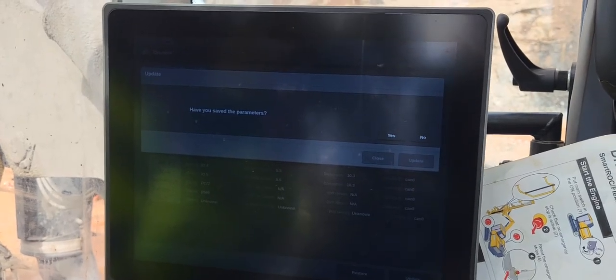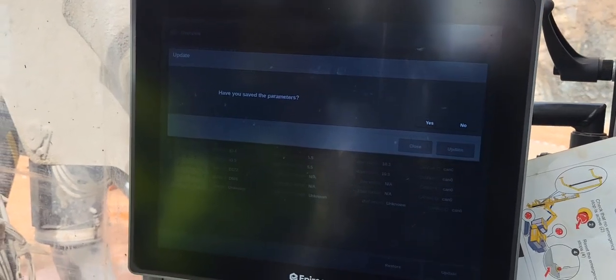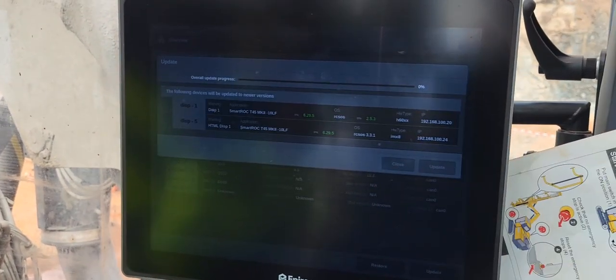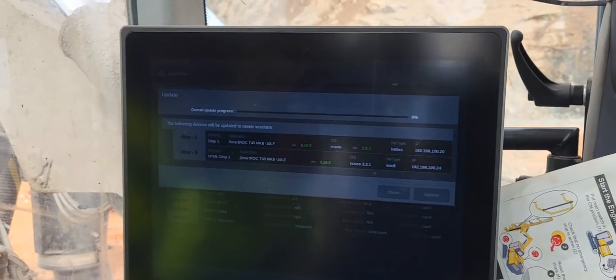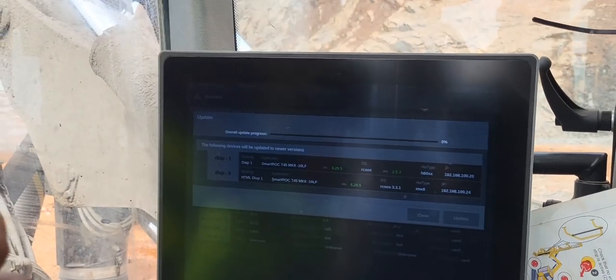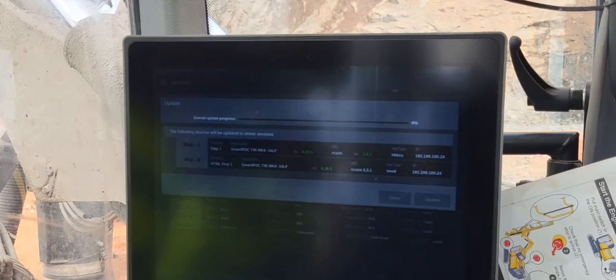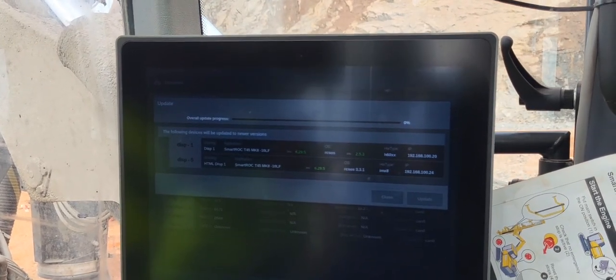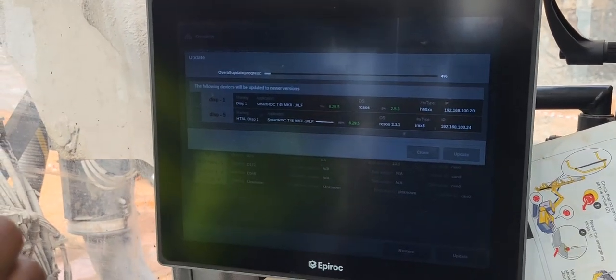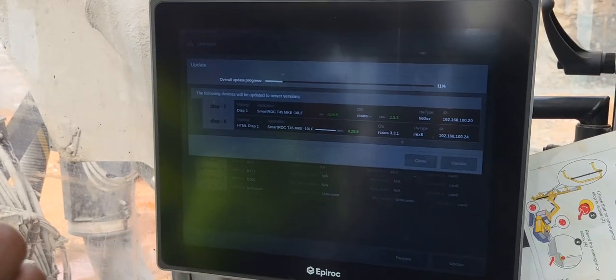So you can see that it's just following the instruction. Now it's asking, have you saved the parameters? Yes, we saved the parameter, so we press yes. If you forget to save the parameter, you just press no, and then you restart. You stop again the RCS, restart without the software in the USB stick. You download first always the parameter, then you upload the software, because if you lose the parameter and then upload the software, you have lost the parameter.